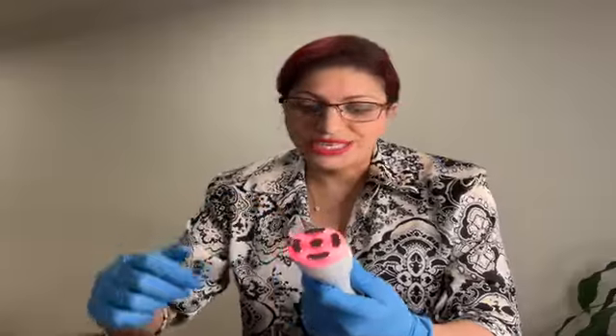So I'm going to spend the next few minutes explaining what radio frequency is. I'm in a bit of an awkward position here, but I'm just going to lean over my model. Essentially, radio frequency has a positive and a negative depending on the device that you're using. It could be multiple positive and negative polarities. But if we have a look at this particular device here, which is the Apollo Duet, we can see it has multiple transducers. These are what we call interferential. So they're both positive and negative, and the energy oscillates between each transducer, creating a homogeneous heating.